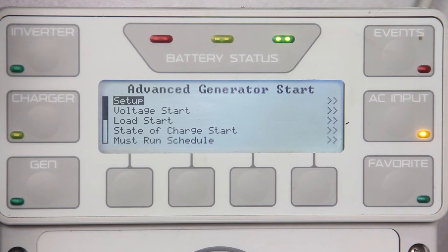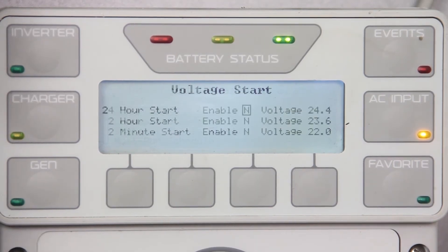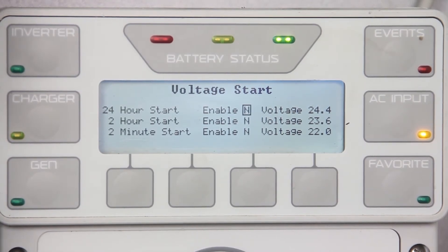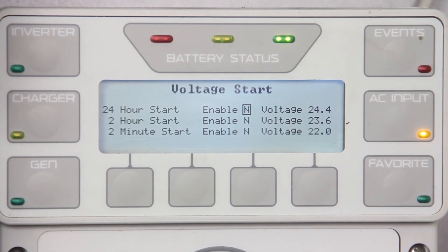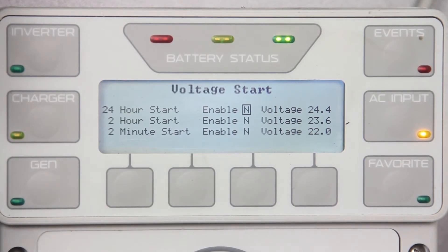Below the description you will find recommended gen start settings. Scroll down to voltage start. Here you have three voltage start set points you may choose from: 24 hour, 2 hour, and 2 minute. If the battery voltage drops below the voltage setting, a timer starts counting down. When the timer reaches zero, a start command is sent to the generator to start. After the batteries have gone through a full charge cycle or the charger's absorb timer, AGS will command the generator to shut off.